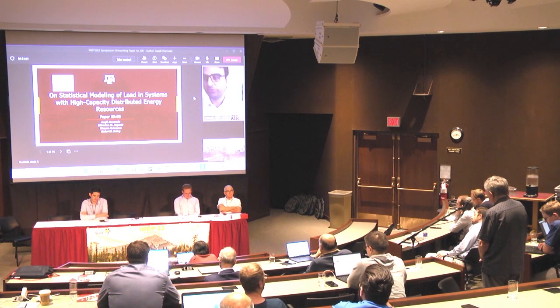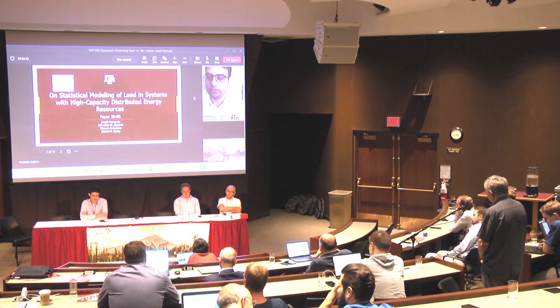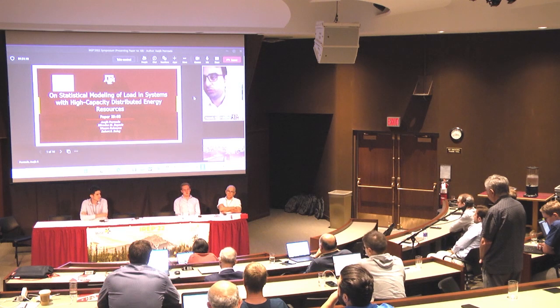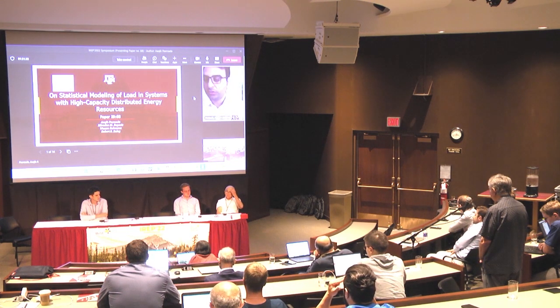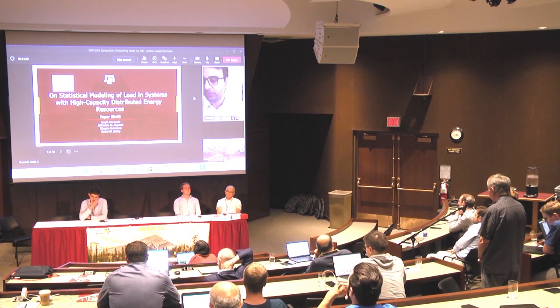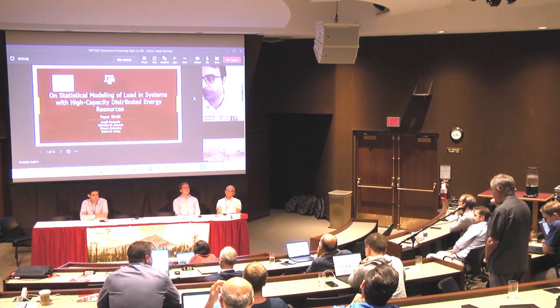Now, of course, if you look at transmission systems, the assumption of a normal distribution is mostly satisfied. It's a reasonable assumption to make, and it gives you reasonable results. But in distribution networks, you have different load types with different energy consumption patterns. Residential loads have a different consumption pattern compared to commercial loads, so you have a wide variety of distributions for loads. In those areas, you might want more precise, more accurate information about how each individual load is distributed so that you can better solve problems such as hosting capacity or sizing power electronic converters. I hope I answered the question.